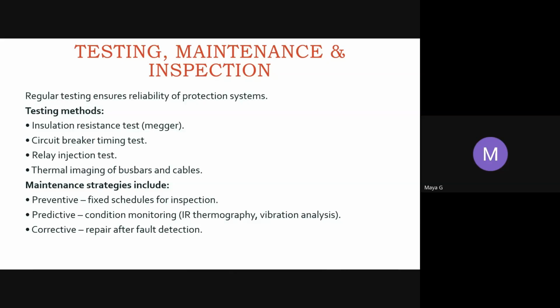Next is the relay injection test. That means we give a test false signal to the relay, for regular testing of whether the relay is operating correctly. We give a false signal to the relay and see whether it operates as per the current rating and the time rating. Then the thermal imaging of bus bars and cables.